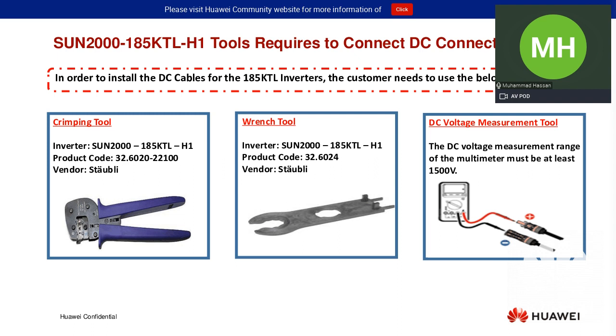Also, you need to use the wrench tool, which is also available with Stäubli. The product code I have mentioned here is 326024. You will use the wrench tool to tighten the nuts of the DC connectors. If any space or any threads on the DC connectors are left, then in future you will perhaps find problems with ISO faults, and you can lose the production of that inverter.